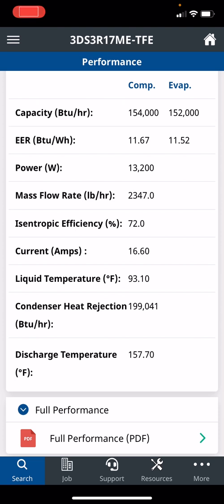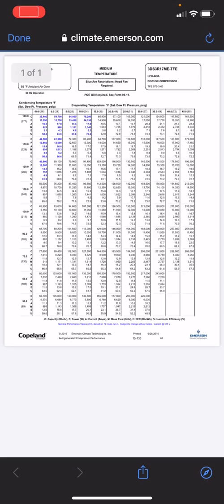You take your temperature probe, put it 6 inches from that service valve, or 6 inches from the compressor on the discharge, and it should be very close to 157 degrees Fahrenheit. Another feature we added was the full performance chart.